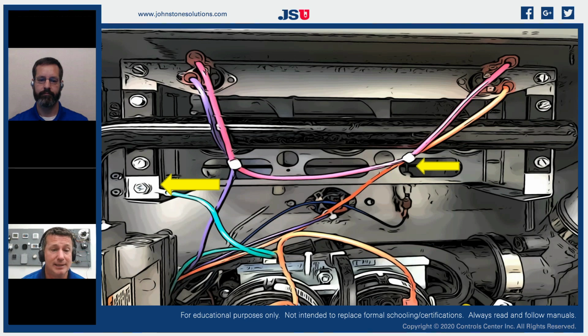That is the circuit that is completing our electron flow for our heat verification, our flame verification, our rectification circuit. So it is as important to make sure that you have proper ground on that circuit as it is to have a clean flame rod. And in a lot of applications, that burner box is sitting underneath of a draft inducer. If we're talking about an upflow 80% or even a 90%, a lot of times our draft inducer is going to be sitting above our burner box.